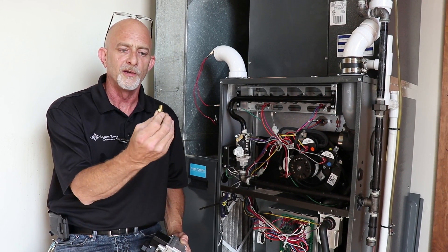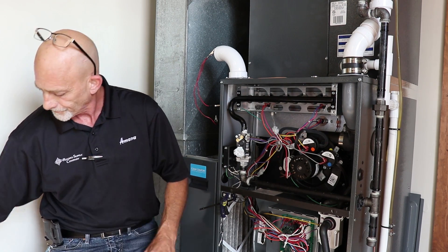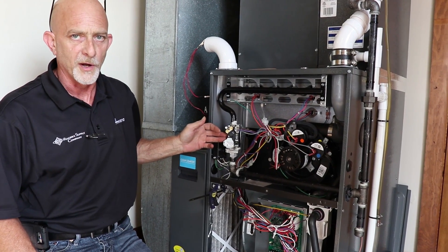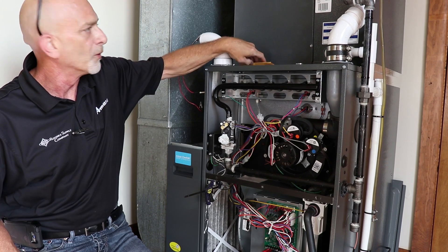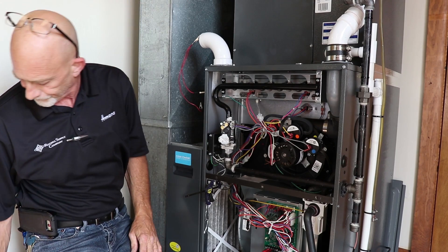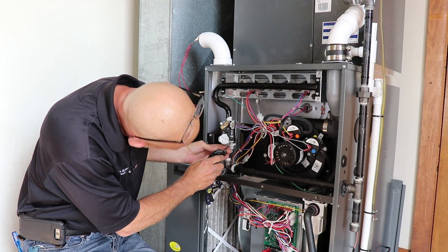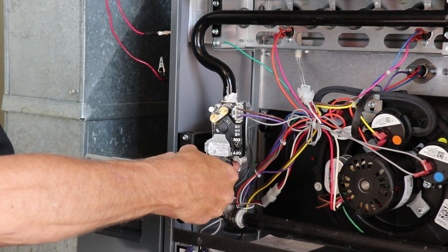You will also need quarter barb fittings to go into the gas valve to hook up your hoses. Let's start with this furnace here — this is a White Rodgers gas valve. First we want to make sure our gas pressure is shut off going to the unit, which I've already done. Take your Allen wrench and we're going to watch the inlet and the manifold pressure at the same time, and we're going to adjust both low and high stage.